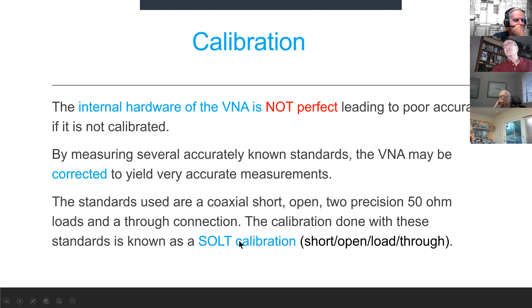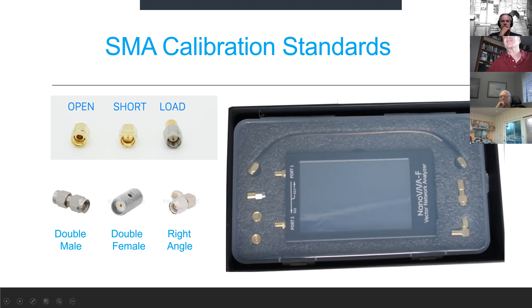And here are all those things. Here's an SMA open, an SMA short, an SMA load. Here's a double male to make a through connection, or a double female to make a female through connection. And for some reason, they give you a right angle as well. Plus, they give you a couple of pretty decent RG316 Teflon coax jumpers that you can use to connect the device under test to the VNA-F. The whole thing is delivered in a nice plastic box, which is included inside a nice stiff cardboard box that does a really nice job of protecting the instrument. So here's a brief summary of the calibration steps.